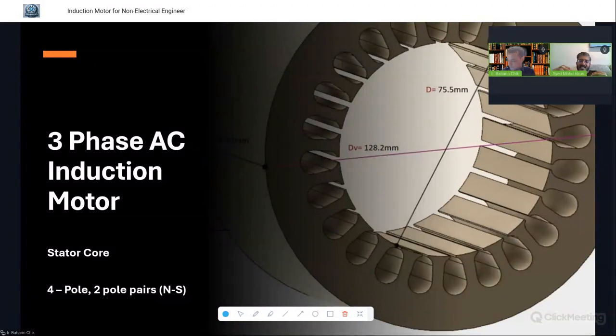Because that is more on the process and selection by the vendor. What I understand from the question is, during the design stage, if the process already identifies a continuous high viscosity fluid, is it better to use a high number of poles on the motor side, or increase the gearbox ratio at the pump? Usually there is a balance between both of them, Cik Barin. But it is not our call, it is more on you. The process gives the process data to the vendor, then the vendor will size accordingly, whether they want to use a VFD or a gearbox, or you don't need anything else, just VFDs. Understood.